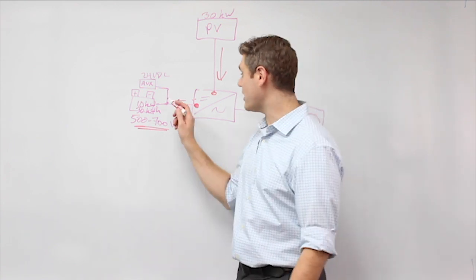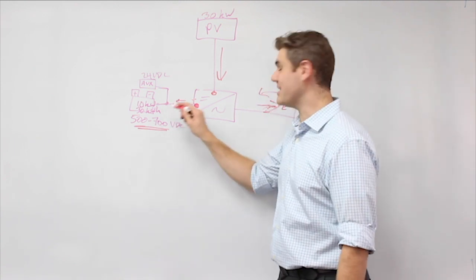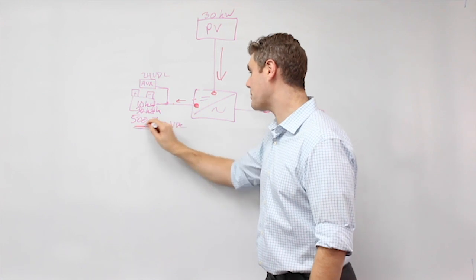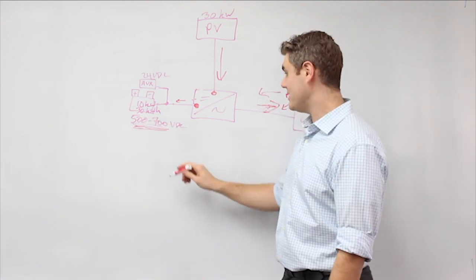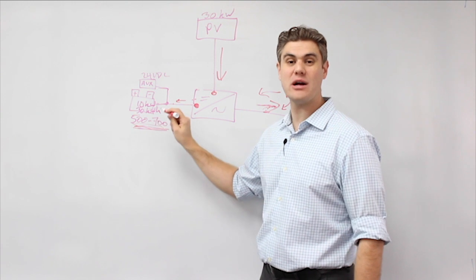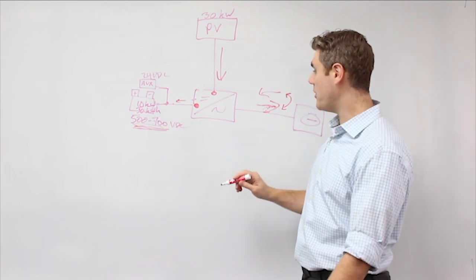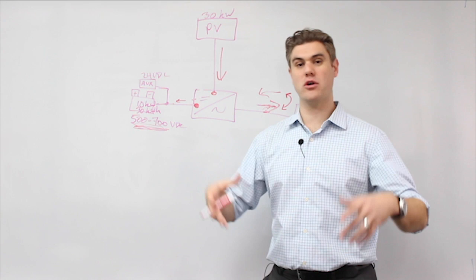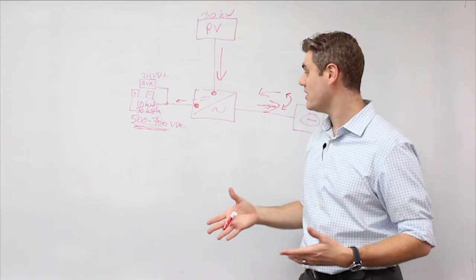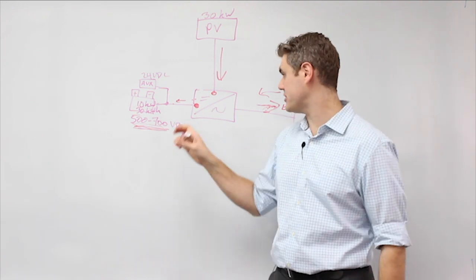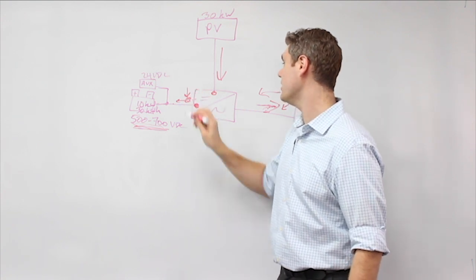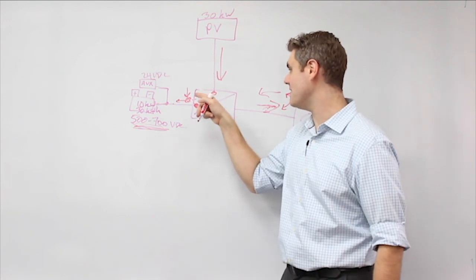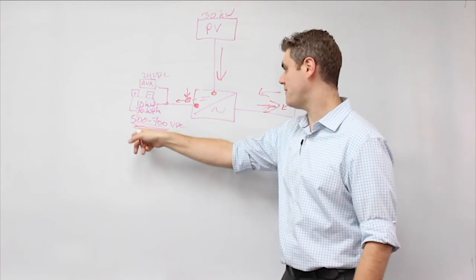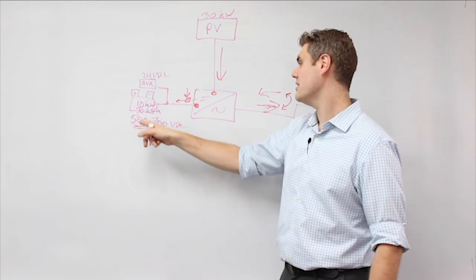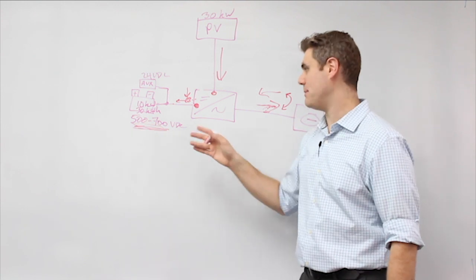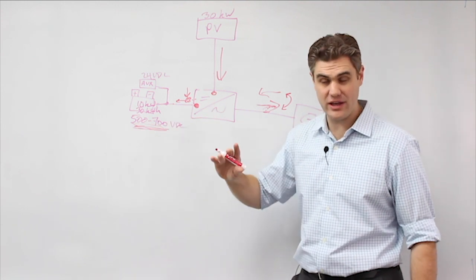The other test that's done is on the battery side. This battery connected to this inverter, what is its operating voltage window? And does the battery actually turn off when you venture outside of that operating window? So they take the battery, put it on a bench or in the field, and they witness test what happens when you force the battery voltage, or the voltage set point here on the bus. What happens when you change that bus voltage to 400 or 450 or 100 or anything below 500? Does the battery turn off? Yes or no? Pass or fail?